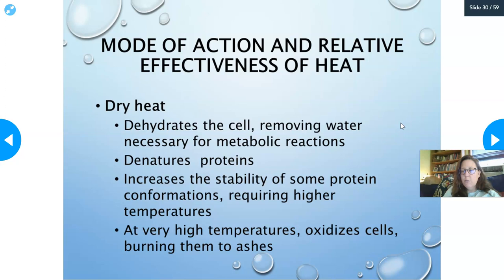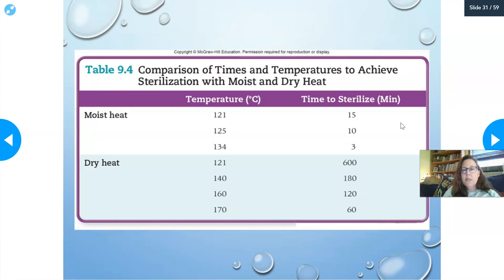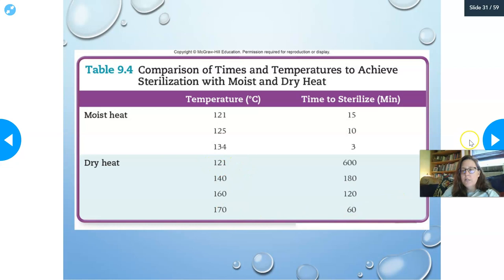Comparing time and temperature: with moist heat at 121°C, sterilization takes 15 minutes. With dry heat at 121°C, sterilization takes 600 minutes (10 hours). Note that 121°C is 21 degrees above boiling. Obviously, at higher temperatures you can shorten the time for both methods.